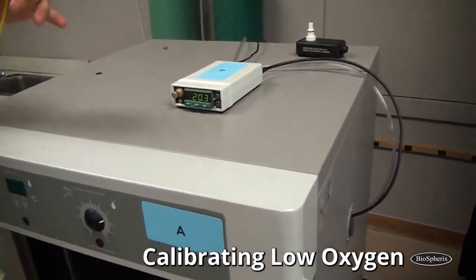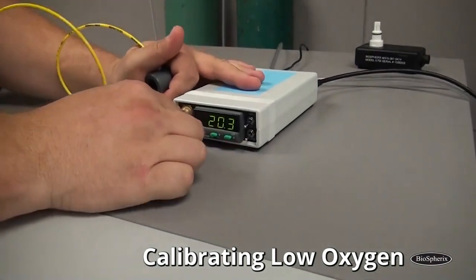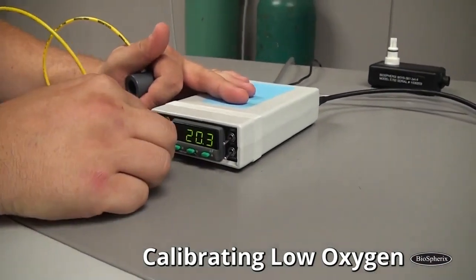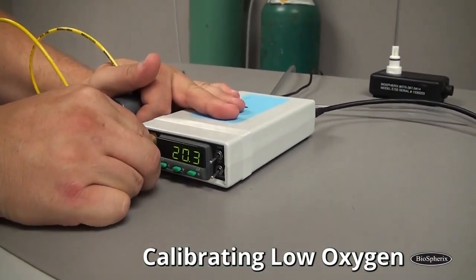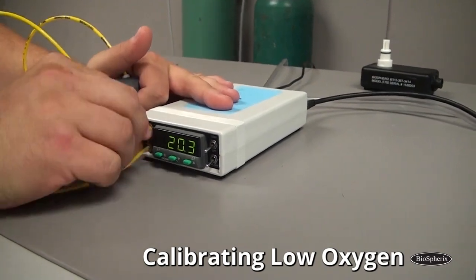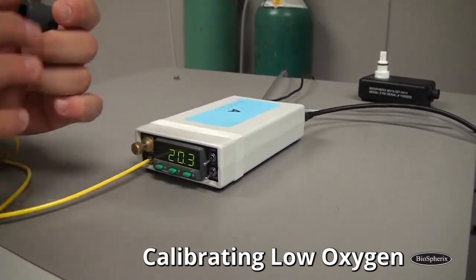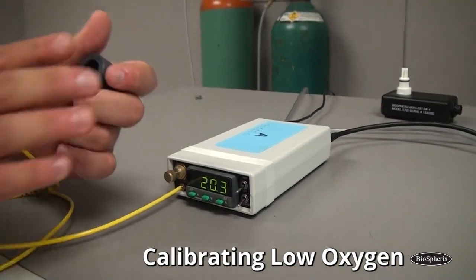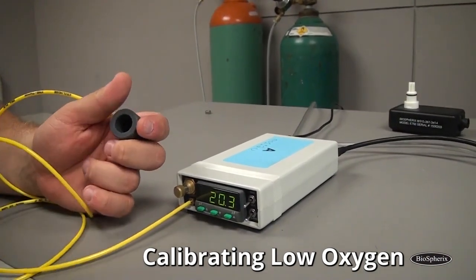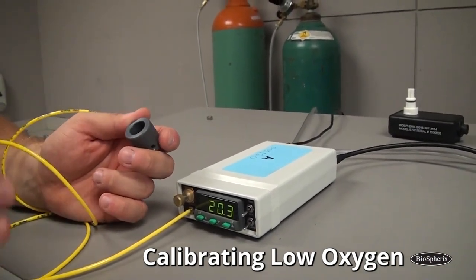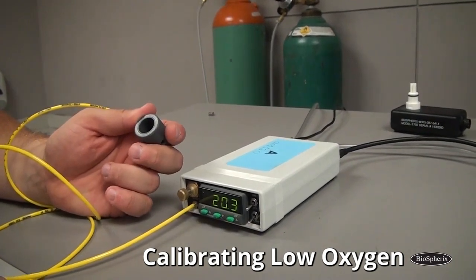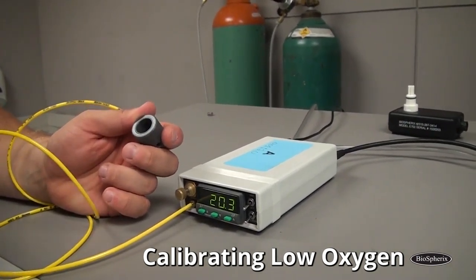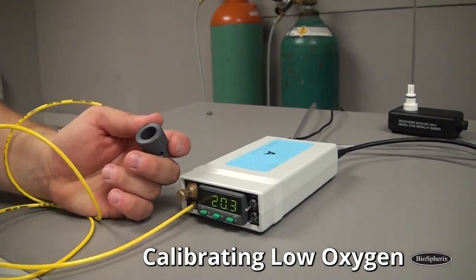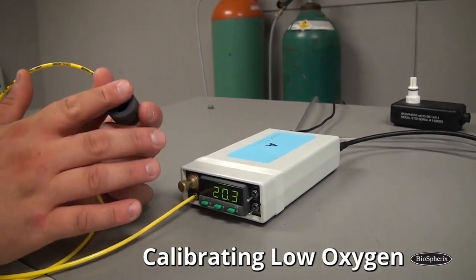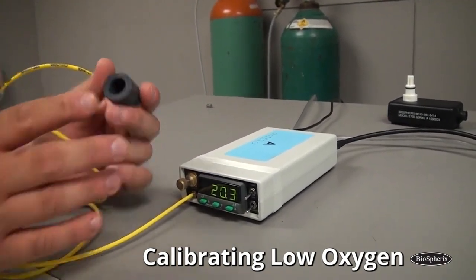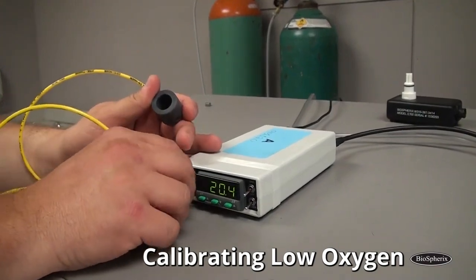So I'm going to hook up the chamber. Just take the end of your tubing, put it right on that bleed valve. You turn that until you can feel and hear it coming out of there. You don't need to crank up the power on there. You can run the risk of over pressurizing the sensor, and that just throws the reading off. If you do that, it doesn't damage the sensor, but about like that, I can feel it with my finger and I can hear it, so I know that's good.